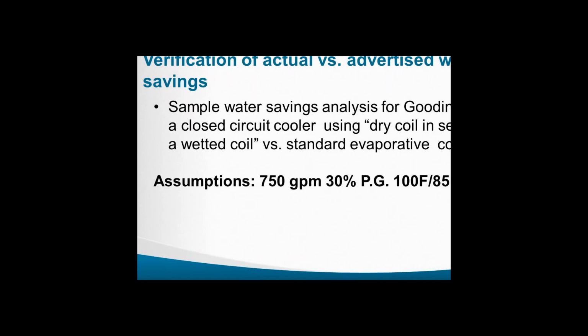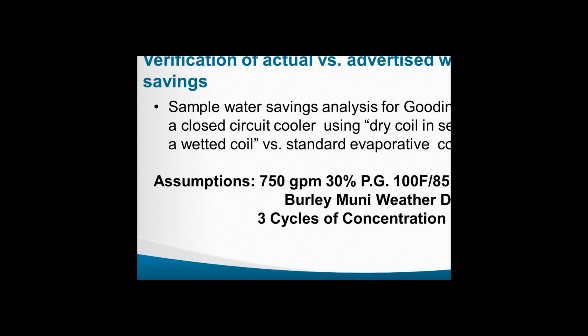Try to verify exactly how your water savings is affected by load, by the weather. So I ran an example. I just used some software and chose this load, 750 GPM, 30% propylene glycol, and those design temperatures. I used the Burley Municipal, I guess it's an airport, weather data.